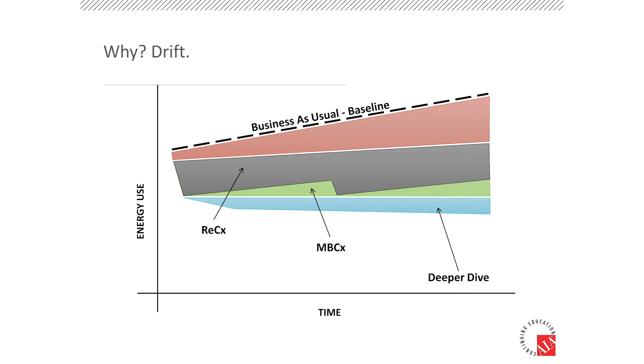So why are we doing this? It's really important to understand a very real phenomenon in buildings, which is drift. There's our business as usual for a building - from day one, buildings drift. Schedules get overridden, equipment starts to fail, somebody gets a cold call in a building, they go adjust a set point, then get pulled off to go fix something. They forget about the set point they adjusted, and it continues and continues, and the energy consumption of a building goes up.